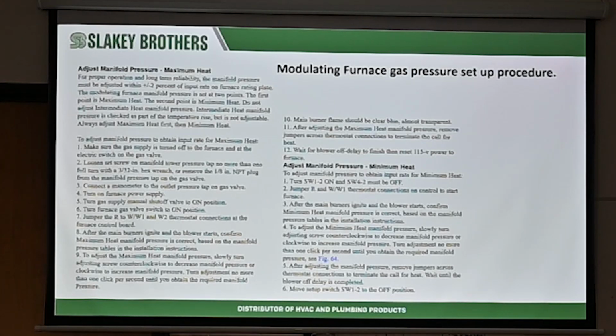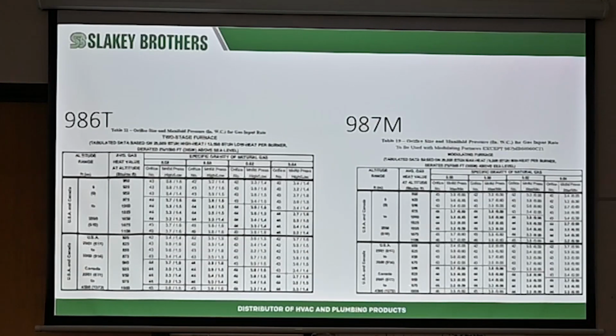After you do it once or twice, you'll memorize it. You never have to look at the book again. But just make sure you set the high fire rate first, then the low fire rate. You'll never have that unit overheat, ever. If the filter is dirty, so plugged up that it can't get any airflow going, the unit probably won't work because it'll shut down because of excessive static. And it'll tell you that there's a problem and nothing will work. And that's how you can find out you've got a plugged up filter, plugged up evap coil, or a collapsed return duct, for instance. Different stuff like that. Otherwise, you'll never ever overheat an Evolution unit as long as you're setting up the gas pressure right. Especially because they're constant airflow ECM motors.